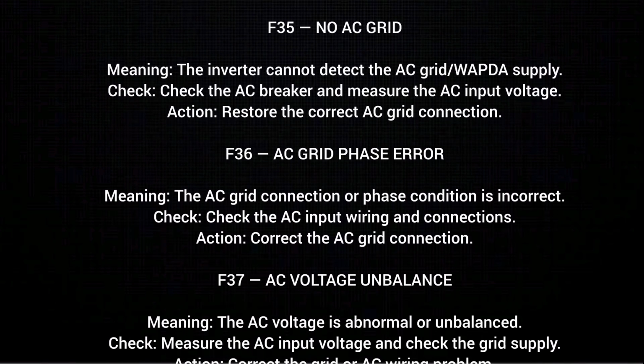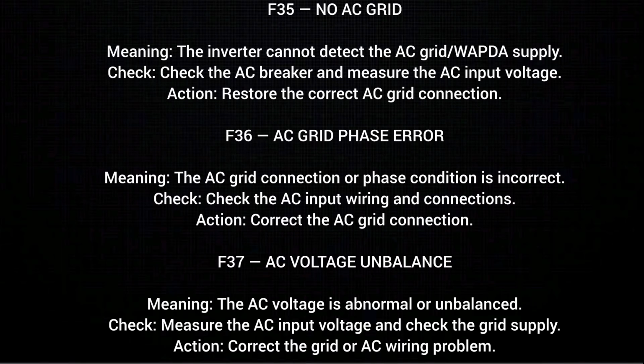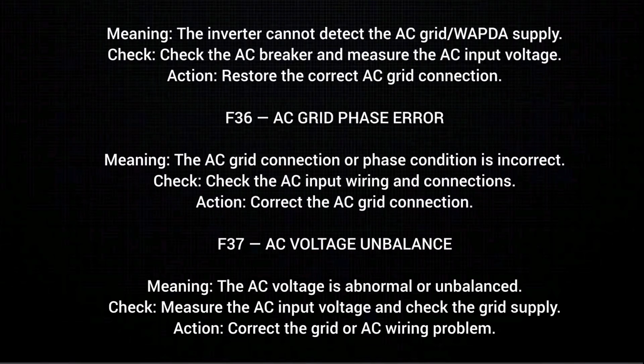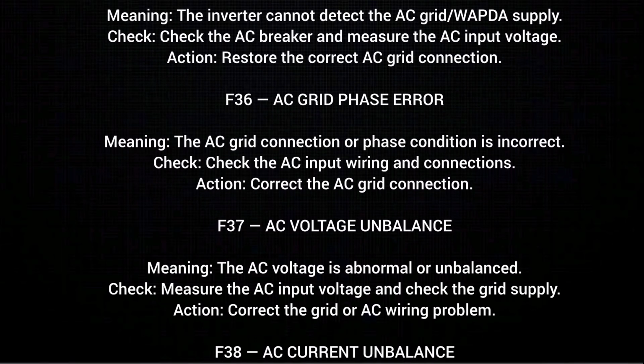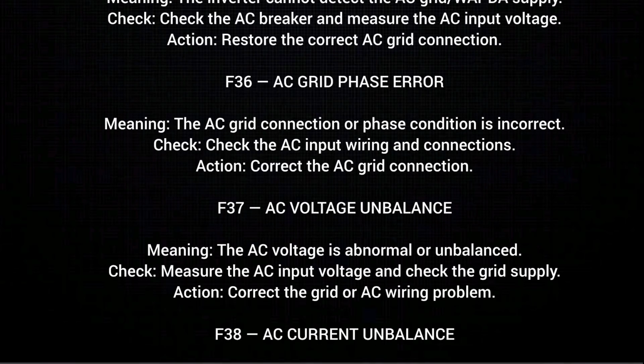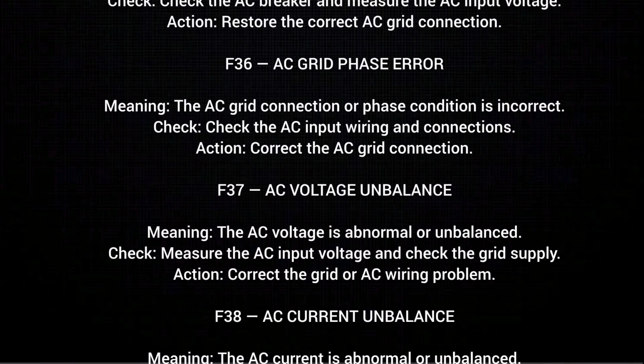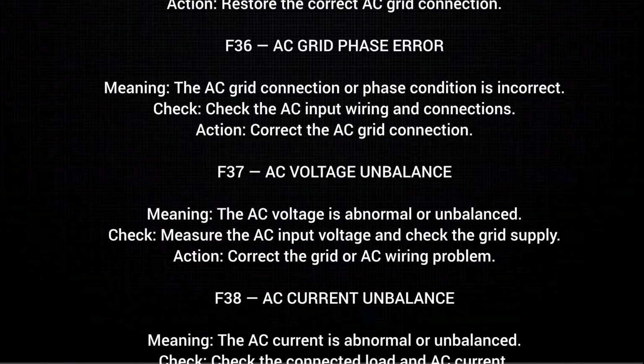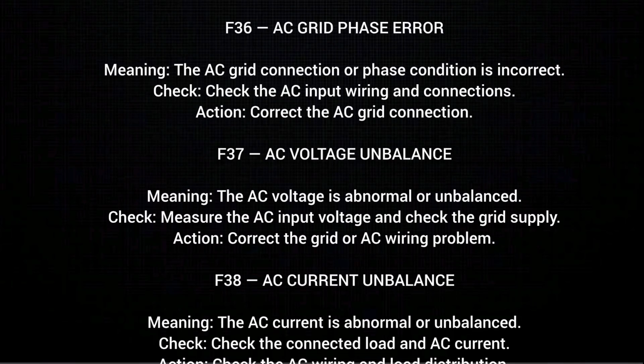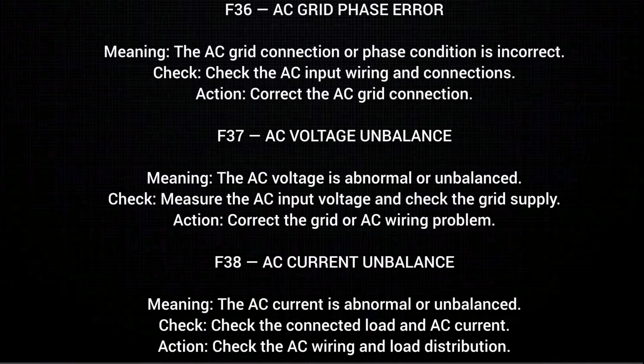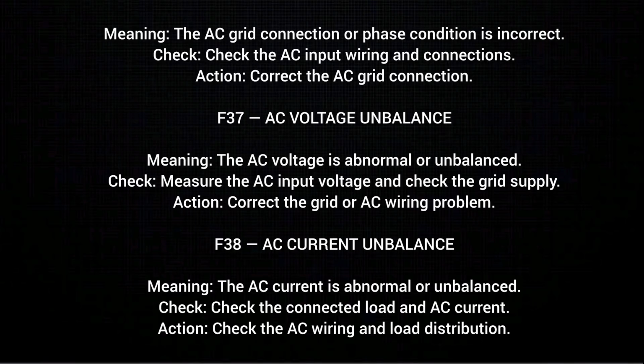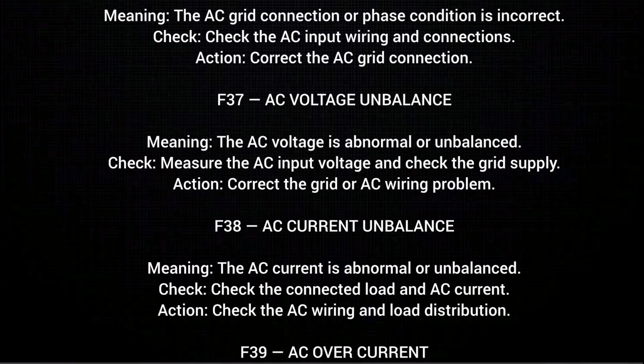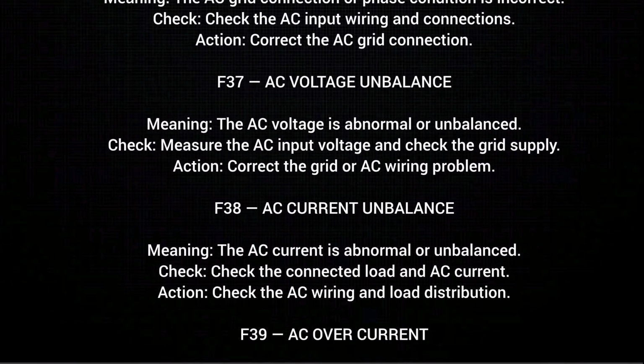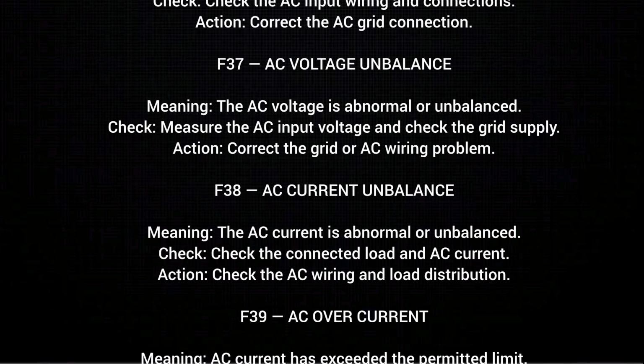F36. AC grid phase error, meaning the AC grid connection or phase condition is incorrect. Check. Check the AC input wiring and connections. Action. Correct the AC grid connection. F37. AC voltage unbalanced, meaning the AC voltage is abnormal or unbalanced. Check. Measure the AC input voltage and check the grid supply. Action. Correct the grid or AC wiring problem.